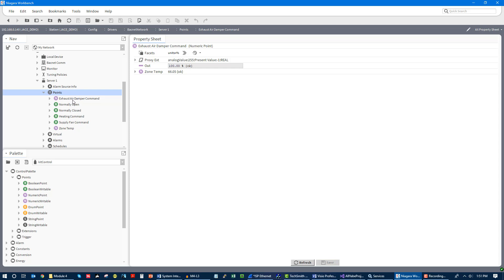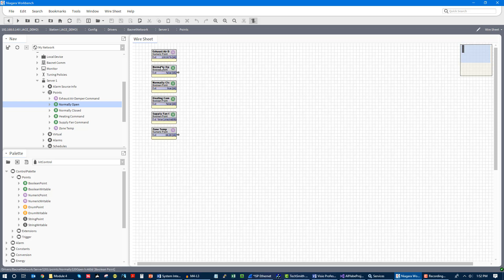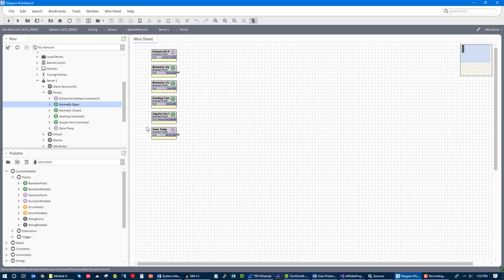Remember when I said that we take inputs, convert them to digital signals, and represent them inside the controller? We actually do that through points. Points are another way of saying inputs and outputs as well as logical. You have analog inputs and you have binary inputs—those are the two physical types of inputs. We've got Boolean inputs and outputs, and we have numeric inputs and outputs. Numerics are another way of saying analog in this particular software. Depending on the software, they may be called analog inputs and outputs or numeric points. We have Boolean, which is another way of saying digital. They may be called digital or Boolean—they're the same thing.